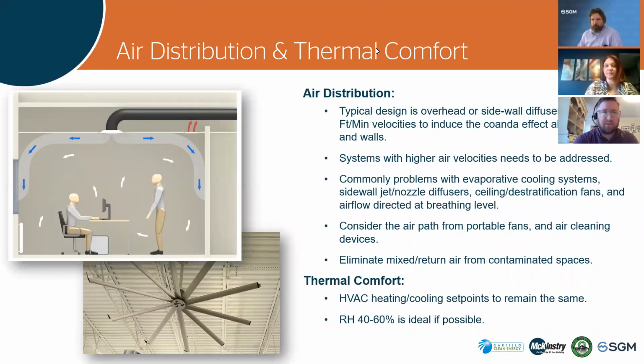One quick note, as Tony said, I really recommend going to the ASHRAE resources. We're going to talk about these general concepts. But in terms of your building, there are specific spaces that need additional scrutiny and may have special considerations. While these general concepts apply, I really recommend getting granular in your analysis, especially for healthcare. Most of what we're talking about here is not specific to healthcare, which has really specialized needs that need to be assessed as such. So I'm going to start with air distribution and thermal comfort. The reason I'm starting with this is that it directly impacts that primary method of transmission of those large respiratory droplets. Someone had a great question about the fluid dynamics in the breathing zone of occupants.